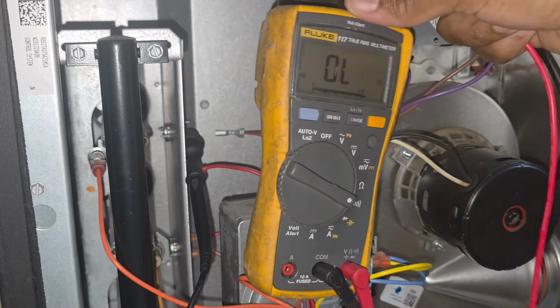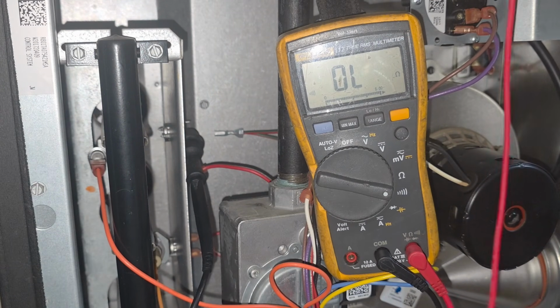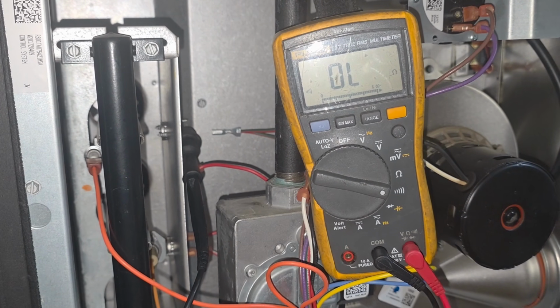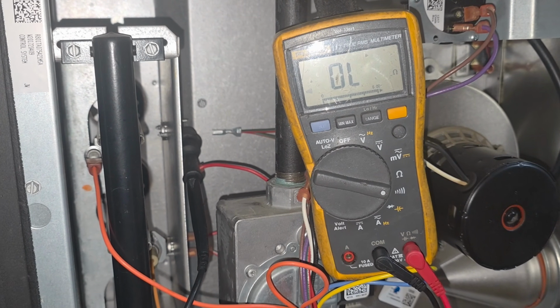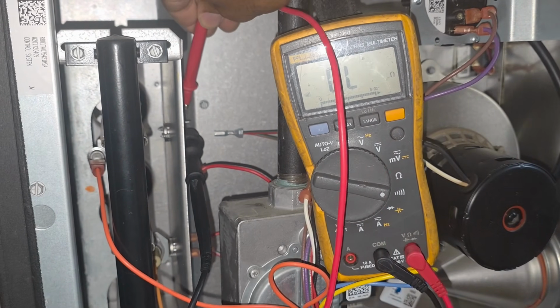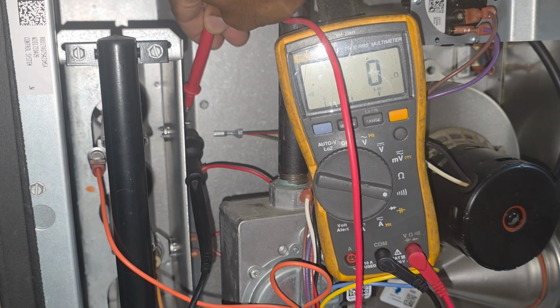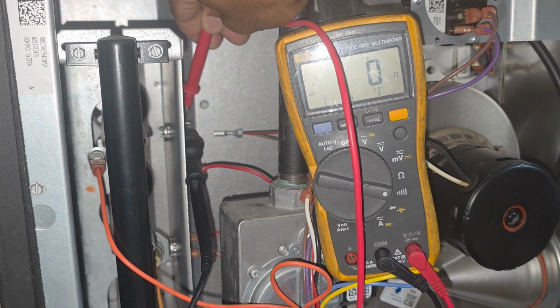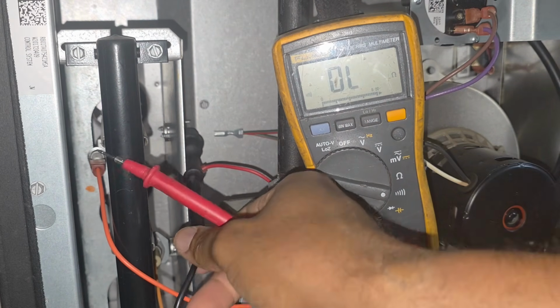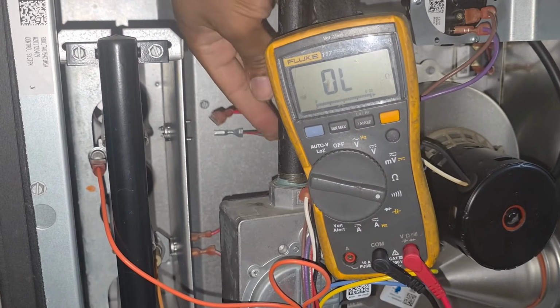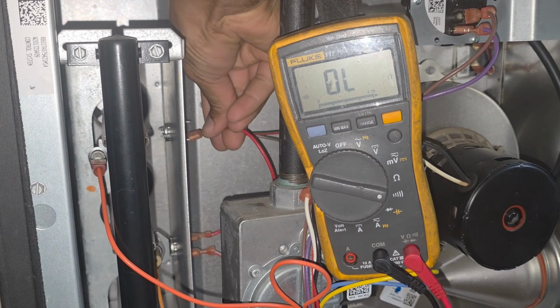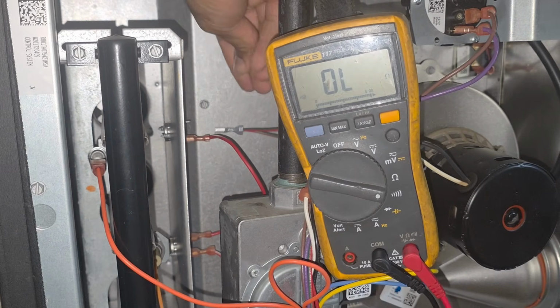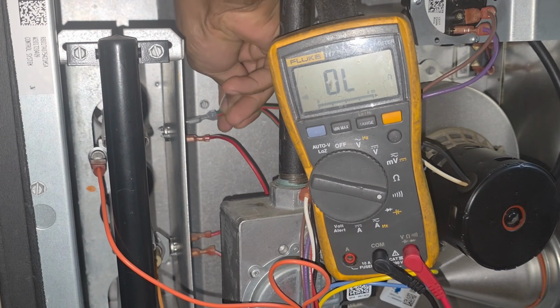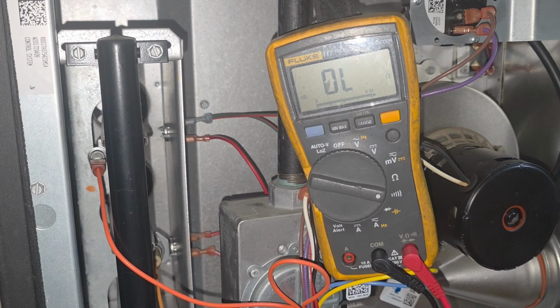But I would turn the unit off, and sometimes I had old helicopter homeowners hovering over me too, and it would take me 2 hours up there trying to find this. But as you see, that switch is closed right there. That means that switch is good. So this is what I would do. So I was like, man, that switch right there closed. So sometimes I would put everything back together and I would call for heat again. Because sometimes if the unit ain't running, that's what you have to do as far as just find the components.